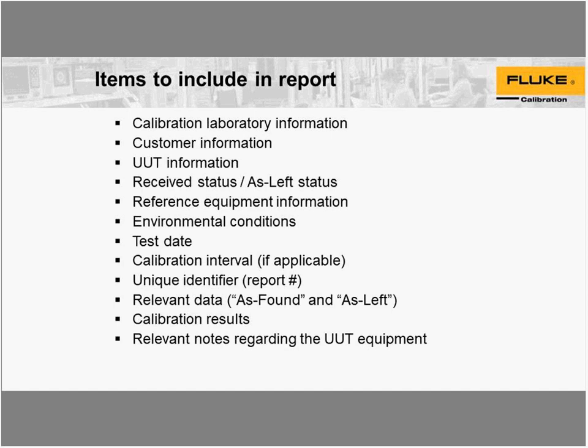Okay, unique identifier. That would be your report number. You could use something as simple as the readout number with today's date on it, or actually go through and put in your own date code system where you're using alphanumerics to generate a number. So you need to have the relevant data, so as found and as left coefficients, and the data from the measurements that you took. All right. You want to have your calibration results. That column where I had written all the P's, so they're all passed, would be the determination of the calibration results.